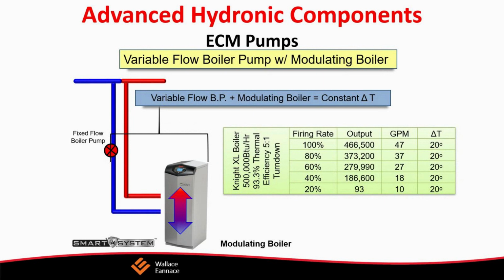Now, if we modulate the speed of the boiler pump to work in conjunction with the rate of flow of the boiler, here you can see at 100% flow rate, the GPM would be at 47. We'd get a 20 degree delta T. As we go to 80, we would drop the GPM to 37 GPM. We would maintain a 20 degree delta T. At 60%, again, 27 GPM, we slow down the speed of the pump and maintain the delta T. Same thing is true at 20% operating. We drop the speed down to 10 GPM, we maintain a 20 degree delta T.